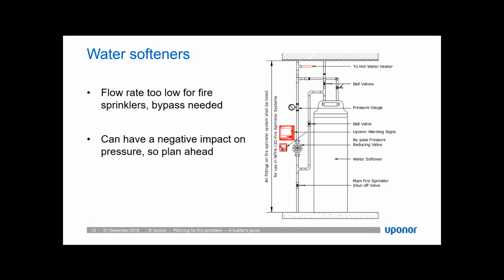So when water softeners are present, NFPA 13D requires that some form of bypass be installed so that when a sprinkler operates, the softener is bypassed and water instead flows at a more direct path to the sprinkler. A mechanical means of accomplishing this bypass can be used by incorporating a pressure-reducing valve.